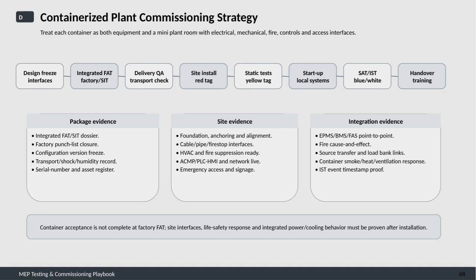Integration evidence involves point-to-point connections for EPMS, BMS, and fire alarm systems, fire cause and effect logic, source transfer and load bank links, container smoke, heat, and ventilation responses, as well as event timestamp proof during integrated system testing.